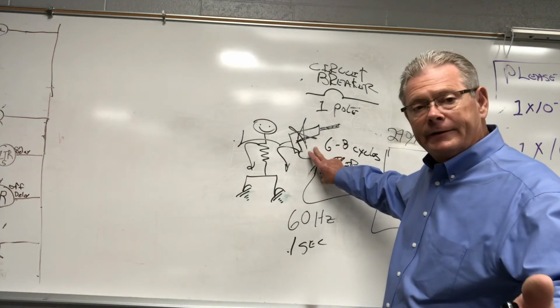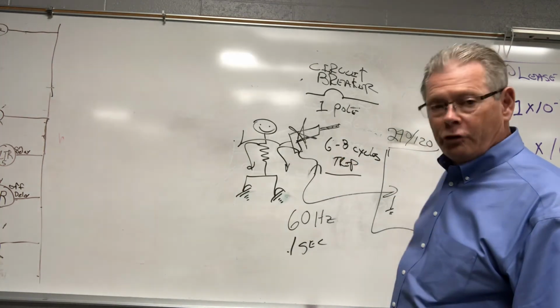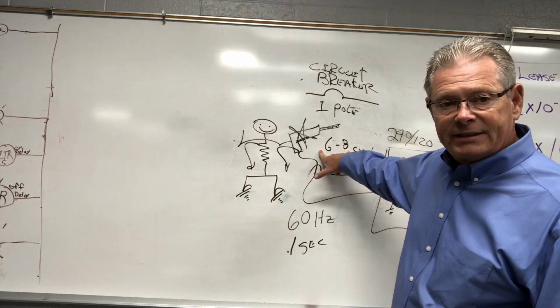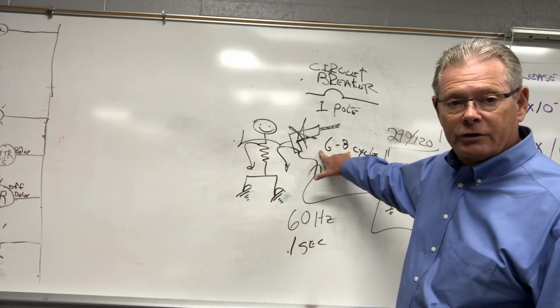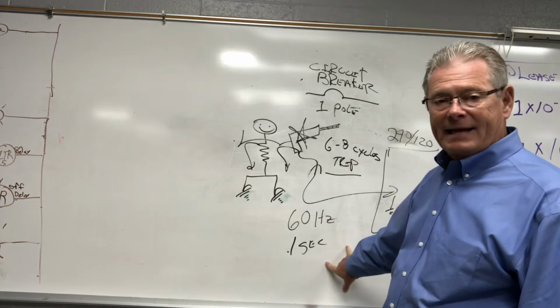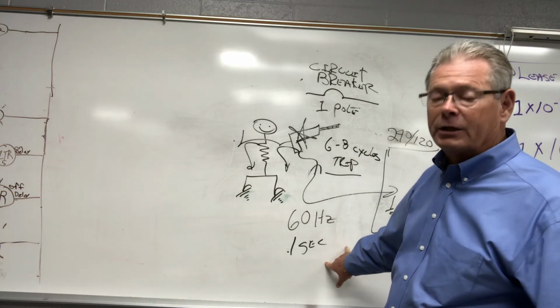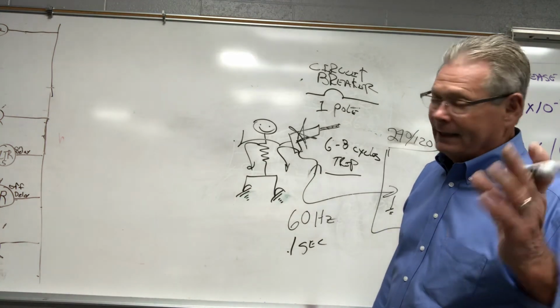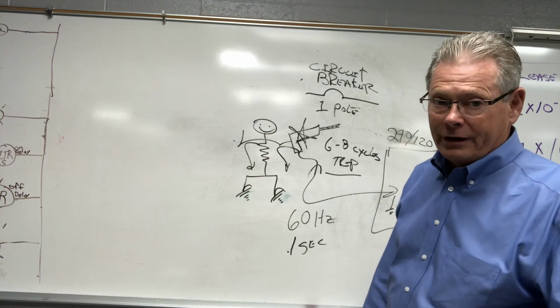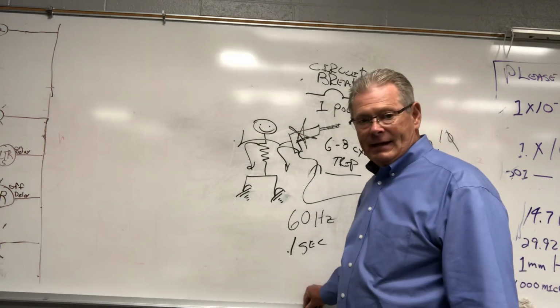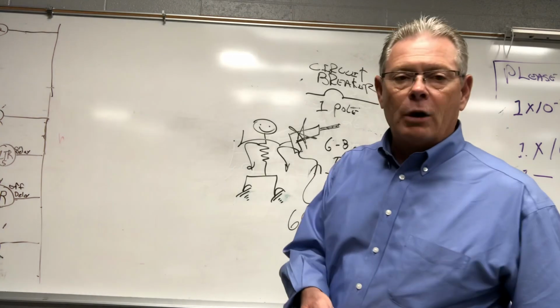Okay, so the answer is yes, you will be shocked, you could be killed. Yes, the breaker will trip, but it takes over 1/10 of a second, at least, for it to trip. And during that time, current's taking all paths because that breaker is trying, it's heating up, but it can't trip. I hope this makes sense, and let me know any questions you have.